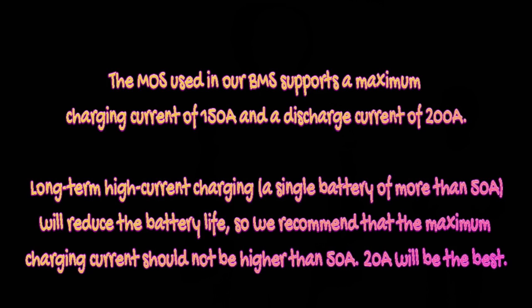Long-term high current charging a single battery at more than 50 amps, which is what it says on the battery, will reduce the battery life. So we recommend the maximum charging current should be no higher than 50 amps to get your 3,000 charging cycles, which is about 10 years of battery life. And they say as a note, and they're going to put this in their manual, that to extend the life of your battery, if you limit your charging current to 20 amps, that's the best thing for your battery. So with 4 batteries, that'd be charging at 80 amps, which is not too bad. But going to 50, you'll get the full life of the battery.